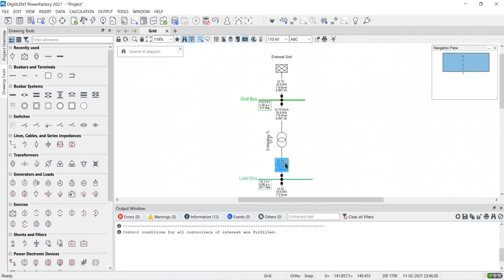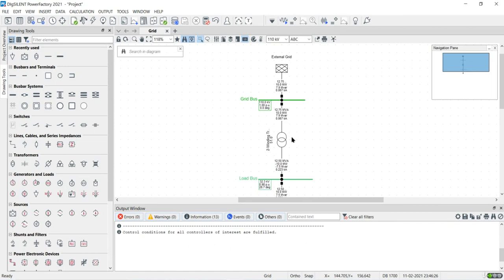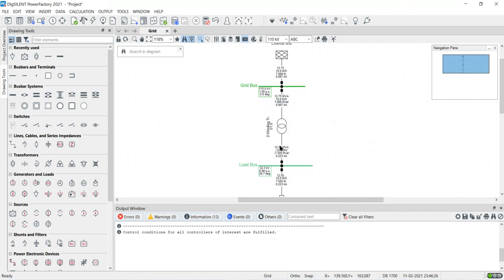So here you can be able to see that the active power which I'm getting from grid it's 10 megawatt, and the reactive power, the loss of reactive power which is in the range of 0.4 MVA. So if I'm increasing the precision, even I can see more accurate values. So here you can see that the loss it's in the range of 0.38 MVA.